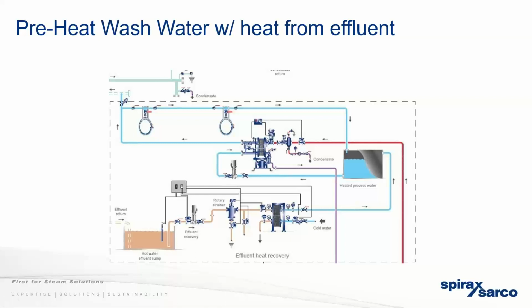Other things we've done is have a buffer tank on heat exchangers, either for high loads or where people just felt they wanted that extra buffer volume. In this application, on the bottom left, we have effluent from the process. A lot of wastewater from the process is going into a sump, and we're using that hot water to preheat the cold water used for washdown. The cold water goes through a liquid to liquid heat exchanger and then into a tank, and this tank is recirculating through the instantaneous heaters out to the hose stations and then back to the tank. So we have a continuous flow of hot water, ensuring that this loop is always at the temperature required for sanitation.